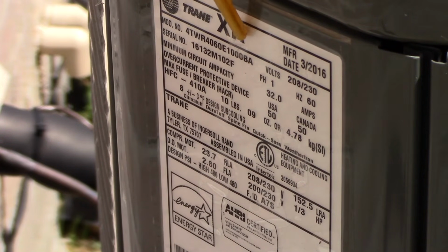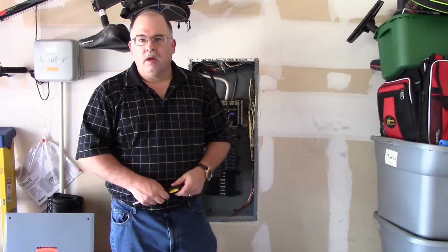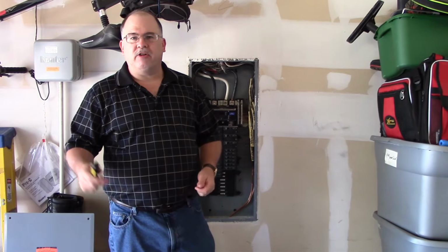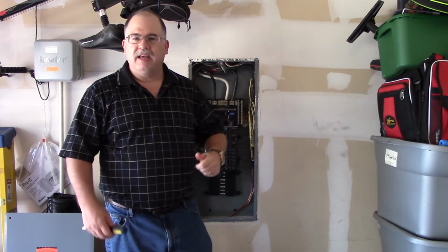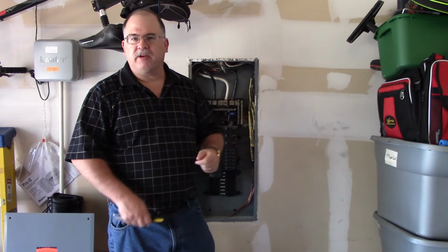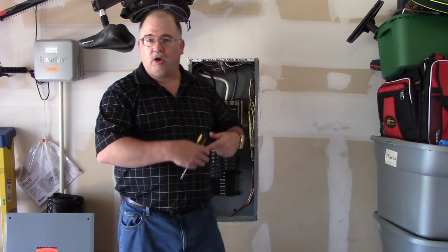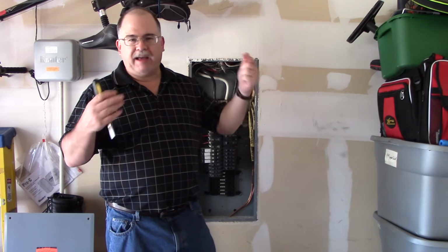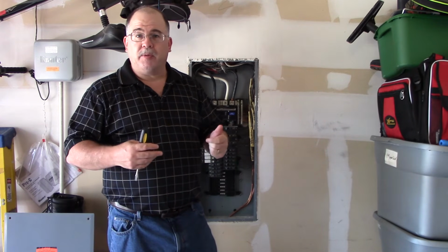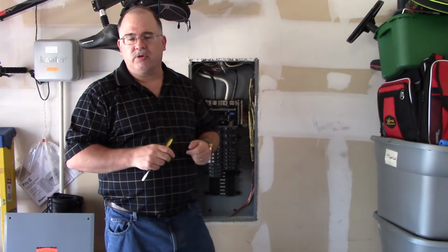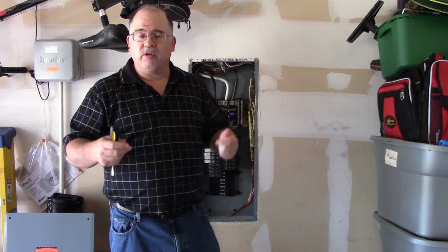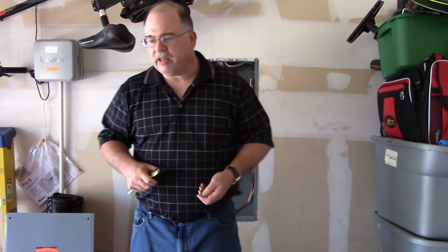But it's real important that you verify that you're dealing with an HVAC system or a motor or what have you, and that's why it's important for that directory to be labeled properly so that you know how to identify this label with the circuit breakers inside the panel. Okay, with our inspection complete, the last thing we need to do is install the panel cover back on the cabinet, and we're ready to go on with the rest of our normal inspection. If you're doing electrical, you're going to check all the receptacles, light switches, all of that within the dwelling. If you're a municipal inspector, you're done with the panel. Now you're going to do your walkthrough and do all your other inspections. Okay, so we're going to move on. So we're going to replace this cover, and then we'll get to that.